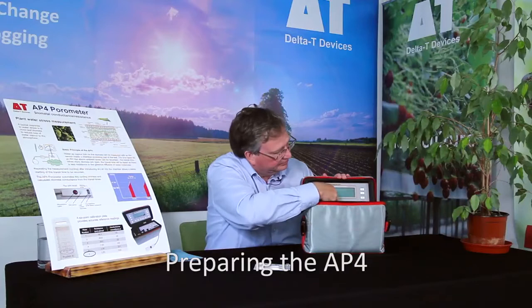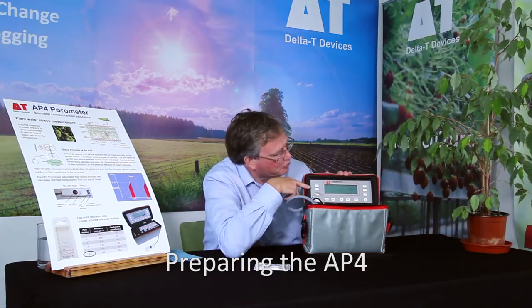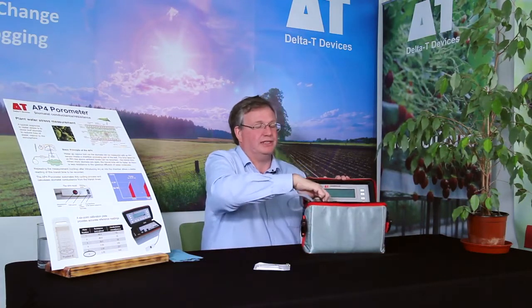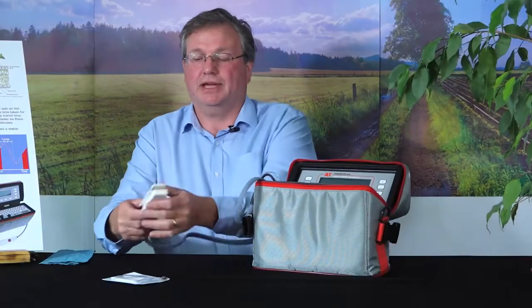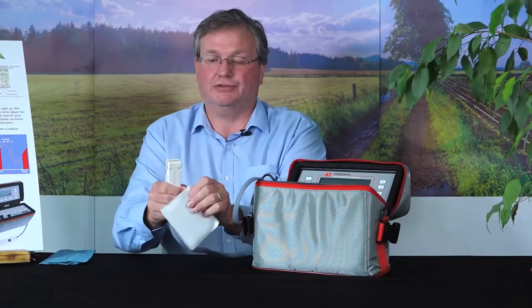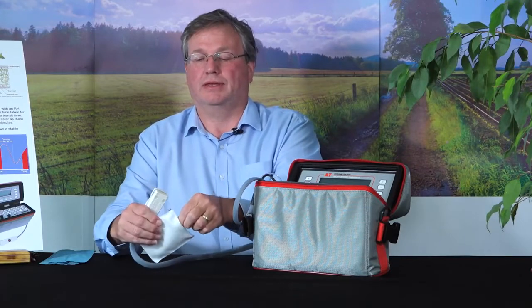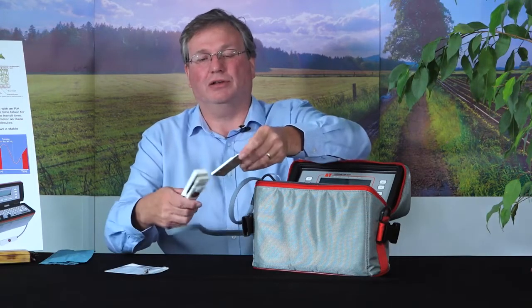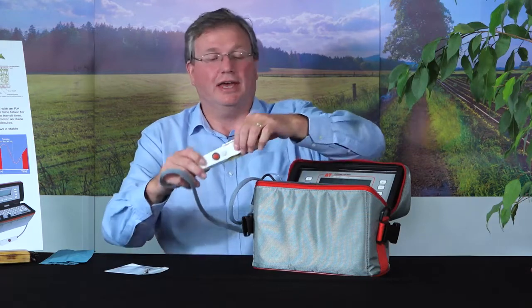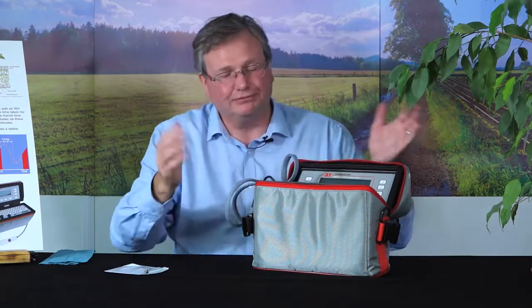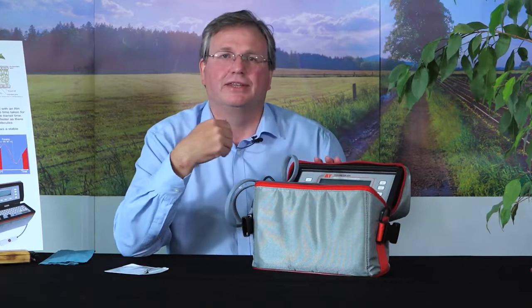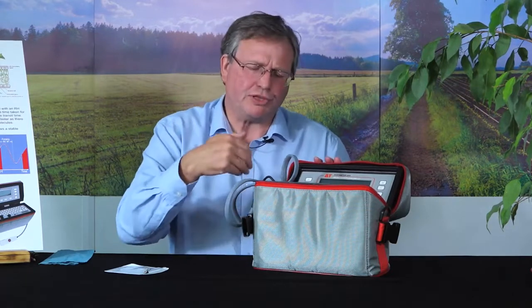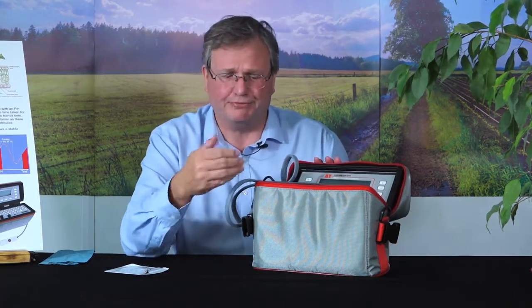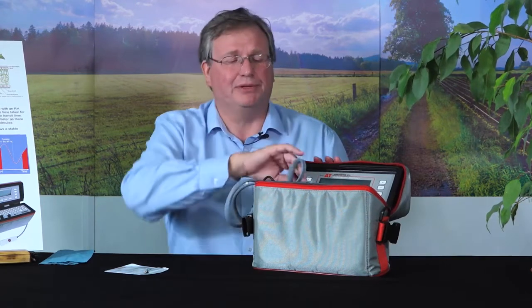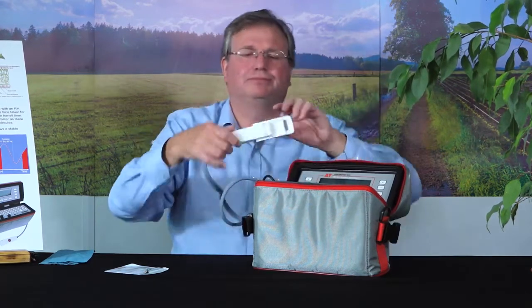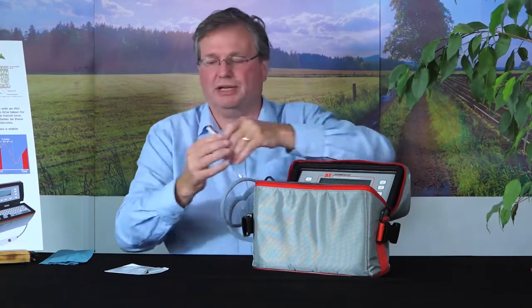Turn the system on, and what we would recommend people doing is to attach the head initially to a plate somewhere halfway along the calibration positions, and place this in the box for 5 or 10 minutes just to let the system equilibrate to the humidity we generated through the wet filter paper. So once you're happy that you've done that and your 10 minutes has elapsed, we're going to continue with the calibration process.